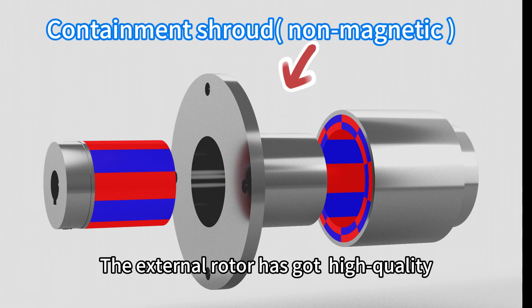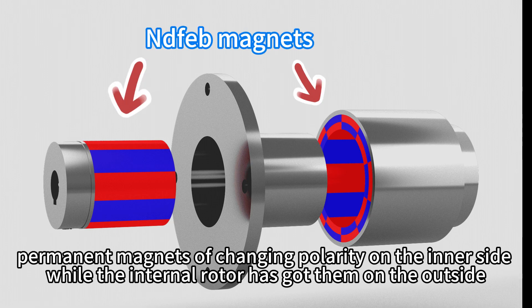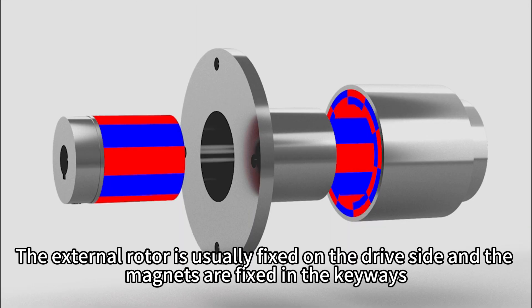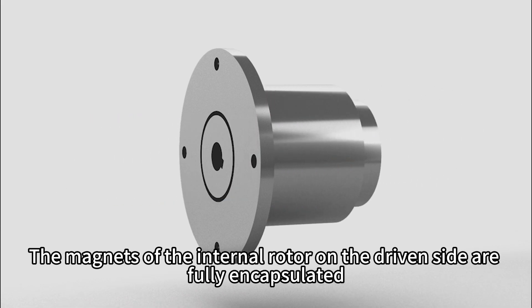The external rotor has high-quality permanent magnets of changing polarity on the internal side, while the internal rotor has them on the outside. The external rotor is usually fixed on the driving side with magnets fixed in the keyways. The magnets of the internal rotor on the driven side are fully encapsulated.